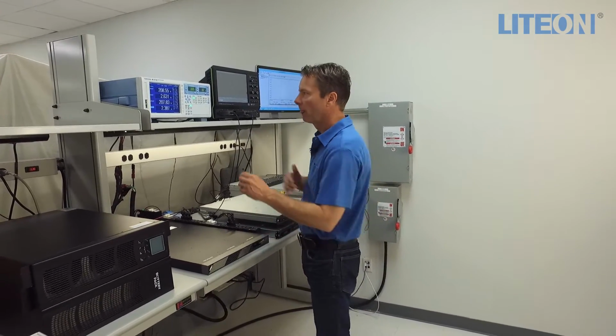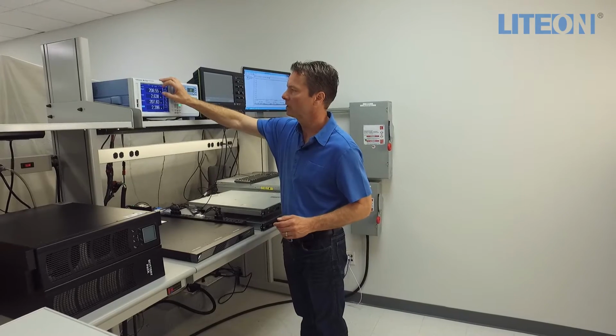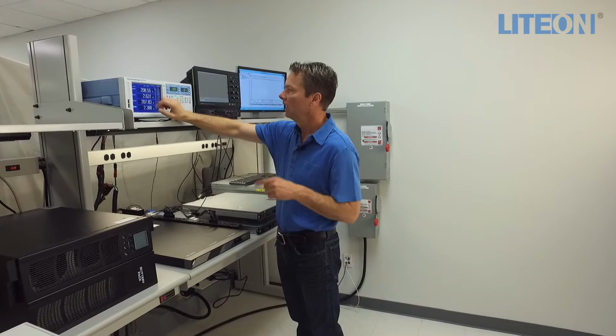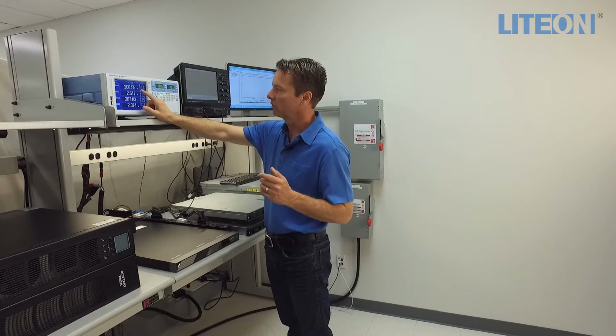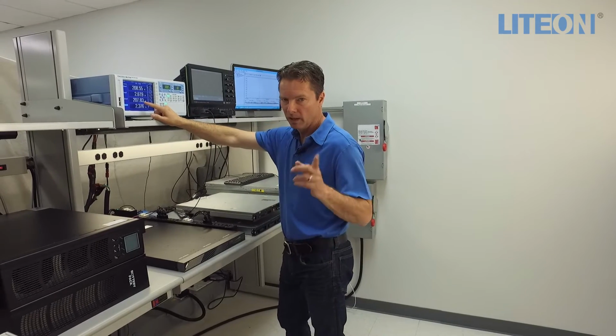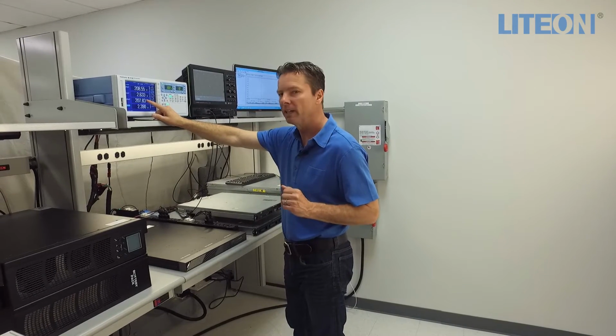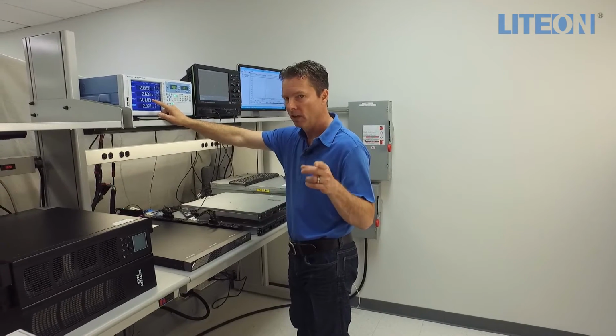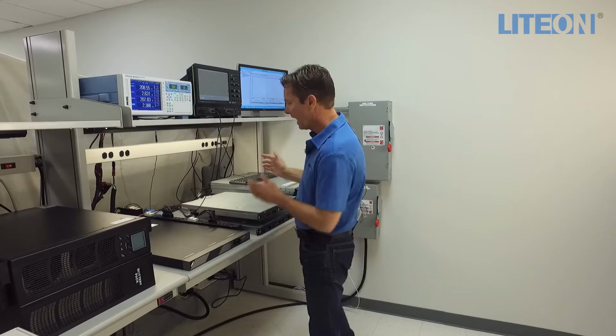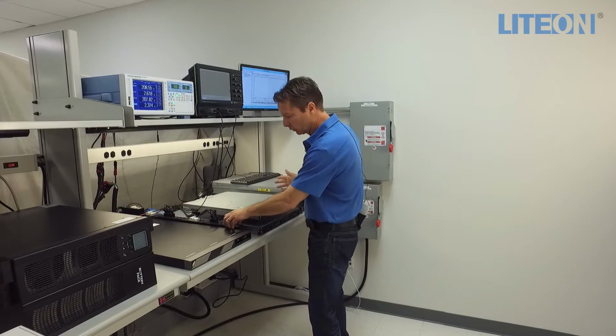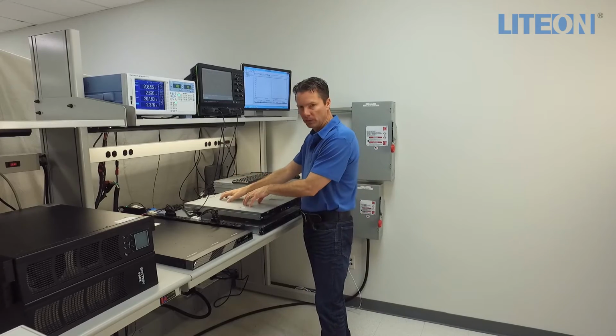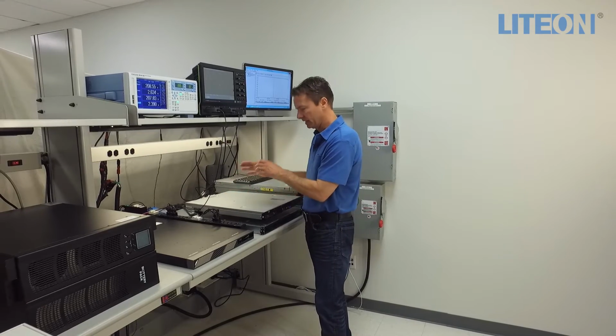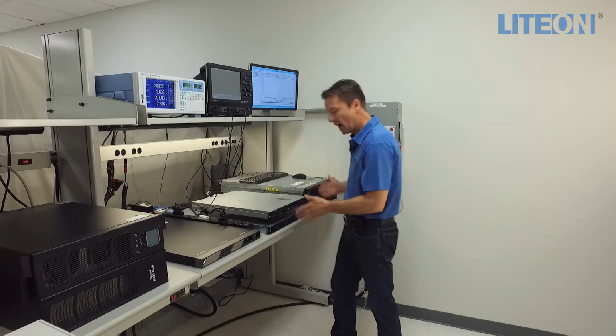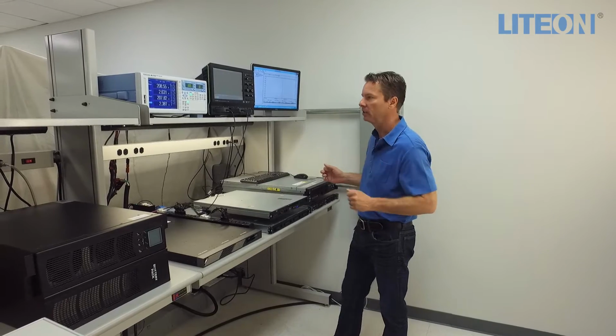When I do that, we'll notice a power loss on the input of VPOC on our power analyzer, and on channel 2 we'll notice there's still a voltage on the output of VPOC, and that the IT equipment, through the PDU and the embedded power supply, is still being fed power to operate as designed.